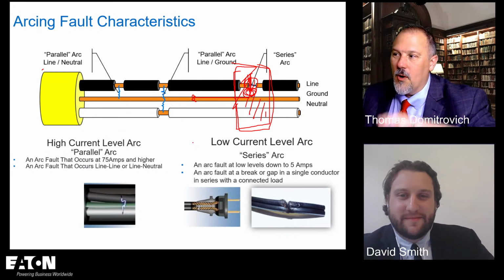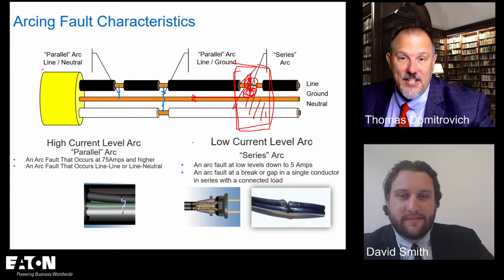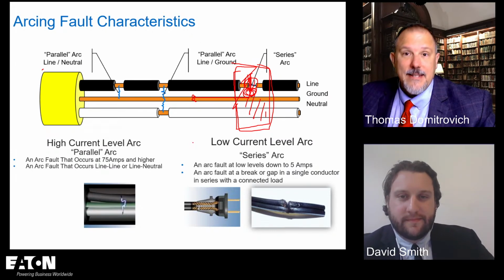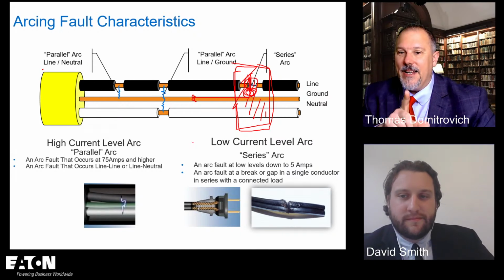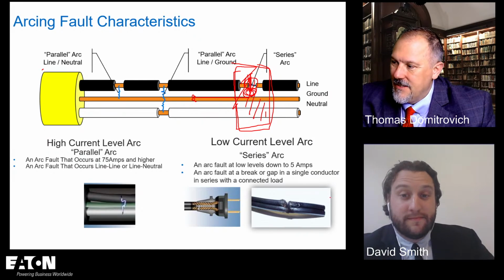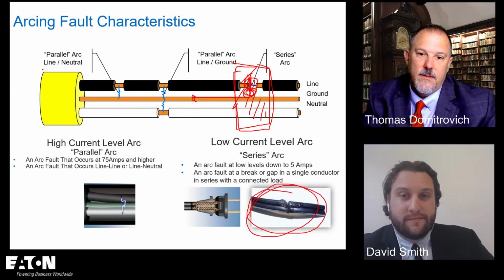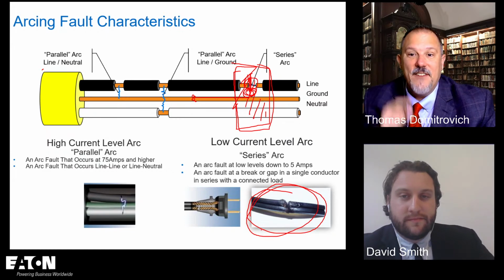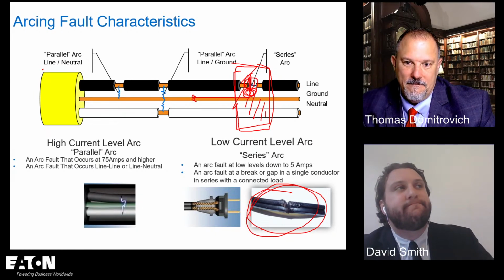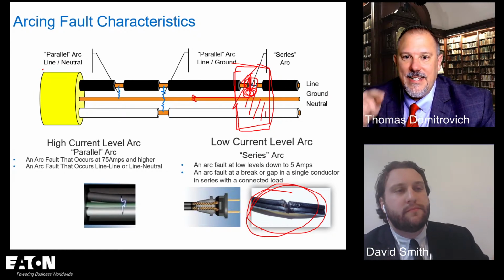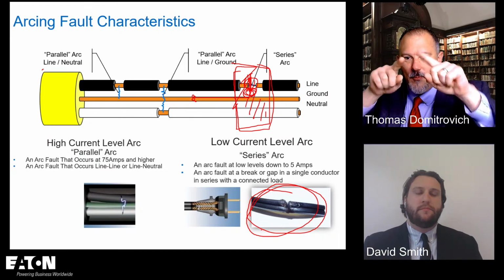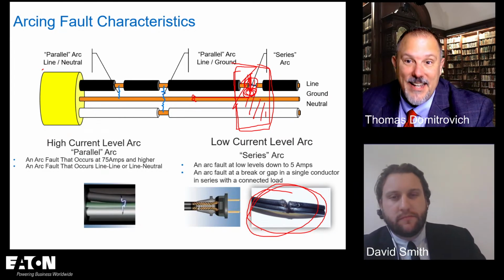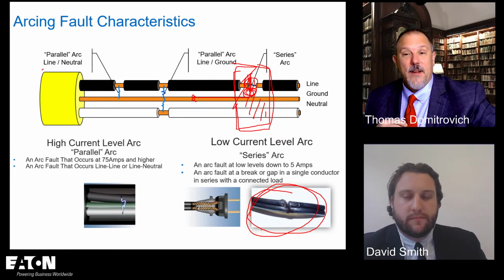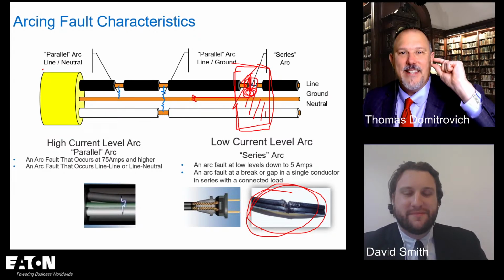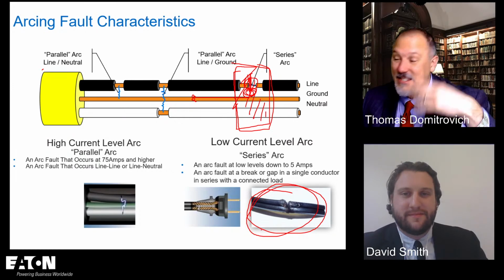And you know what? When we were arguing about the requirement around combination type AFCI, we made presentations to Code Panel 2 saying, why? I can detect a 5 amp series arc. Yes, I use GFPE, but you know what you would not detect? When I've got SPT2 cord, that SPT2 cord does not have an equipment grounding conductor inside. And the test in UL 1699 takes an SPT2 cord, we cut it, we split it back, and there was a debate. Dr. Engel made the arguments that says that's not a series arc to test, it is a parallel arc to test. And technically, I think he was right.